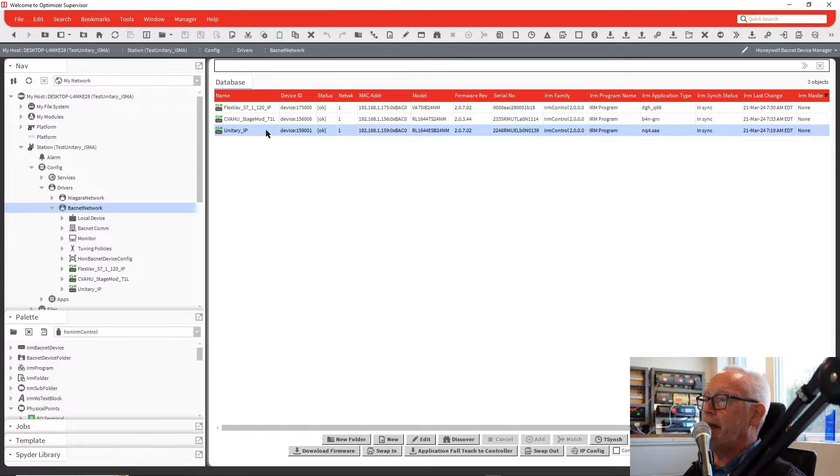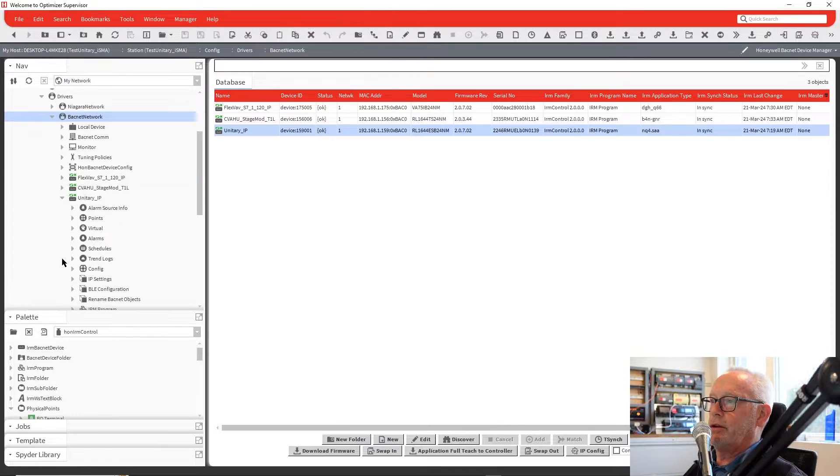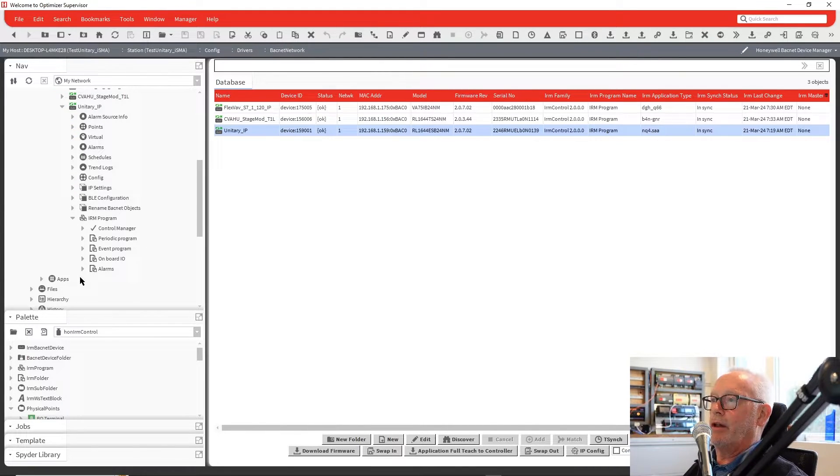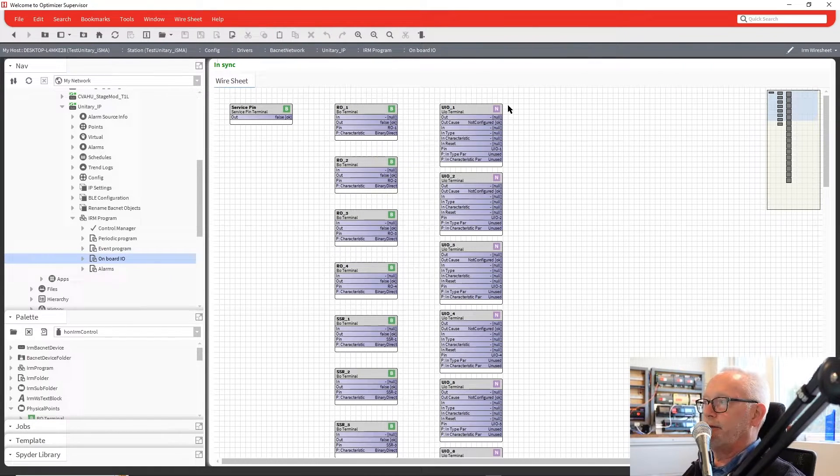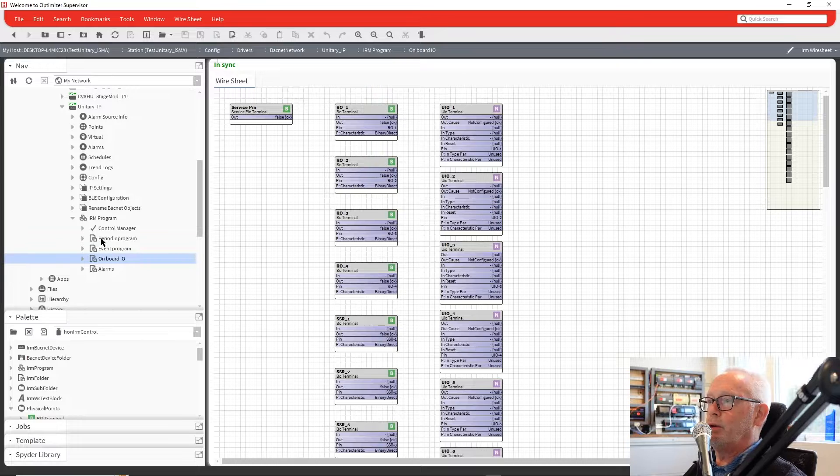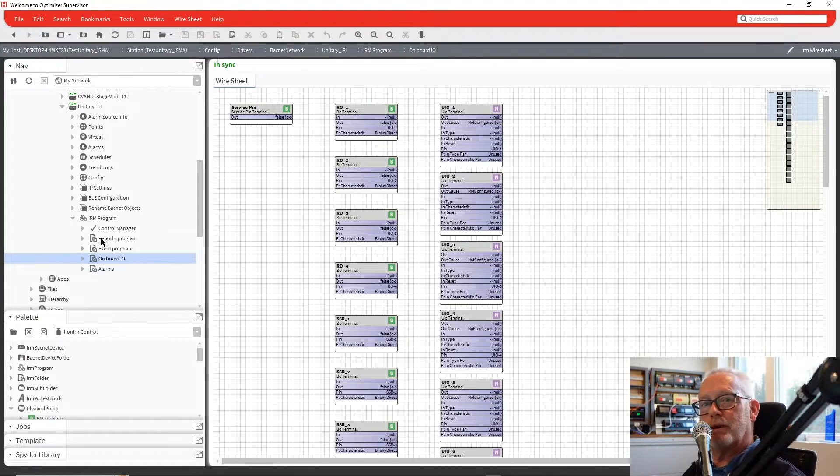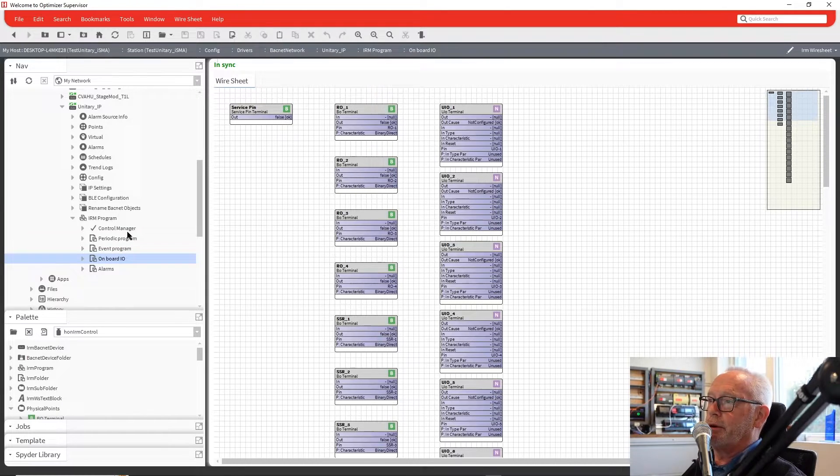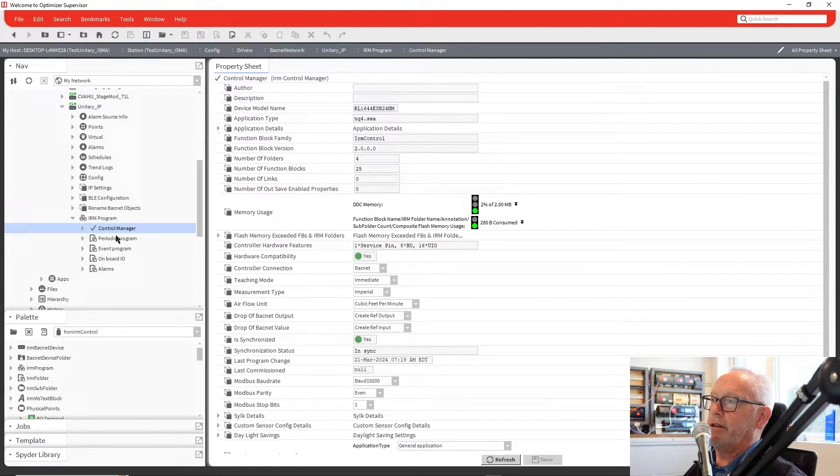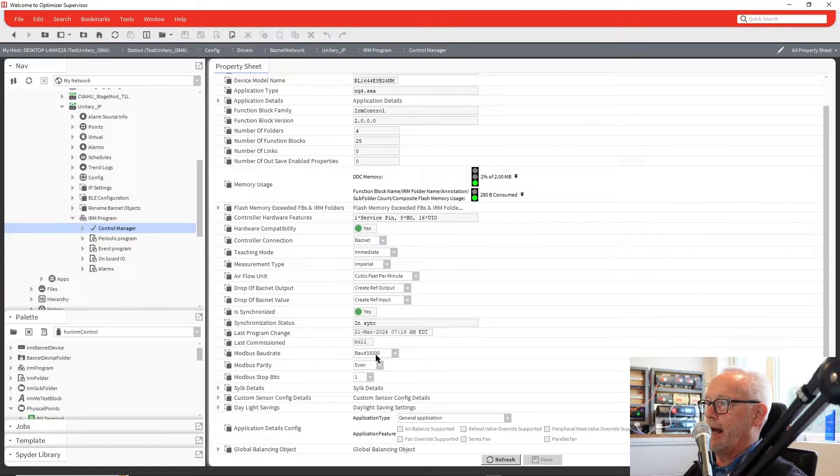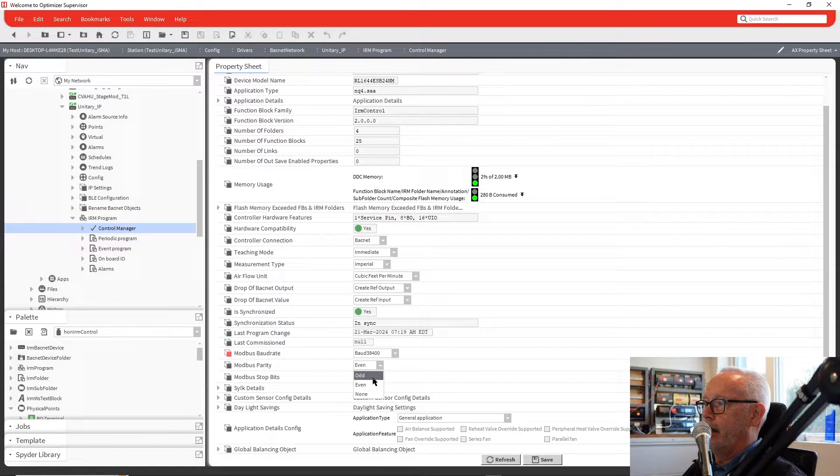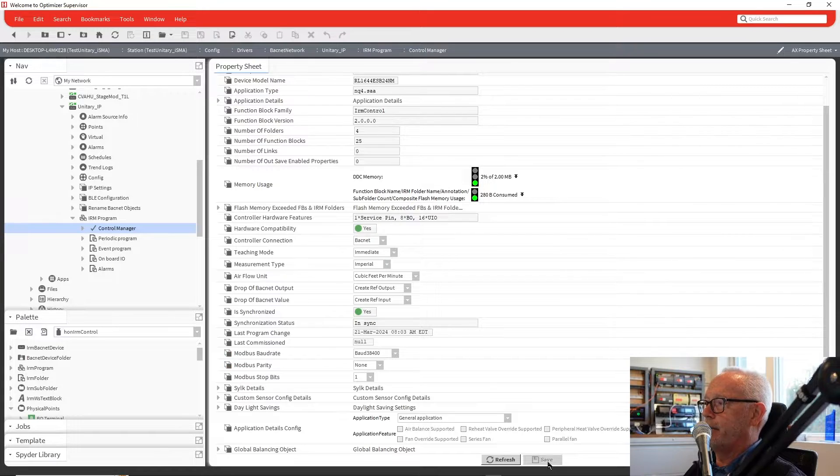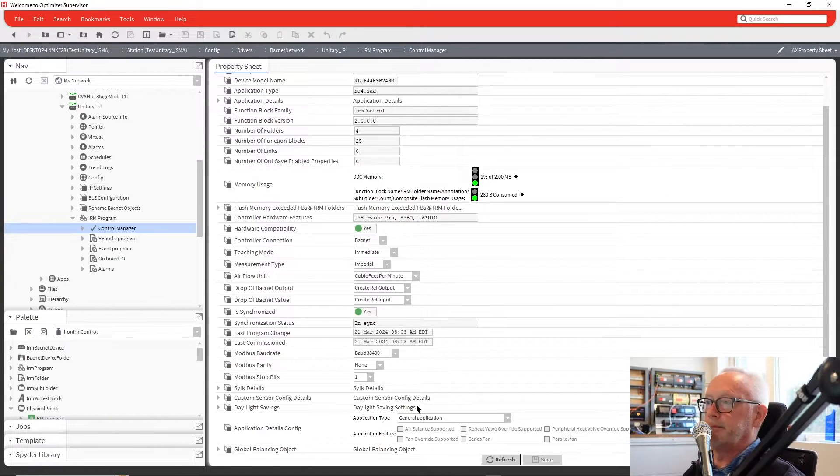If I go to the unitary IP controller, this one's blank. All I have listed in there was just the physical I/O. I just want to show how you would configure the Modbus and add the Modbus device and build it from scratch. First, we would go and look at the control manager. Within there, down towards the bottom, you'll see where you have your baud rate. We're going to be using 38.4, and it's going to be no parity and one-stop bit. We would say save for that. Now the port is set up to bring in a Modbus device.